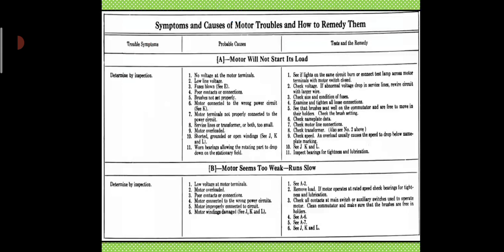Okay. If these problems occur, the tests and remedies are: see if lights on the same circuit burn, or connect a test lamp across the motor terminals with the motor switch closed. Check voltages if there is abnormal voltage drop in service lines. Rewire circuit with larger wire. Check size and condition of fuses. Examine and tighten all the loose connections. See that the brushes seat well on the commutator and are free to move in their holders. Check the brush settings. Check nameplate data. Check motor line connections. Check transformer. Check speed. Overload usually causes the speed to drop below nameplate marking. See the belt and coupling, and inspect bearings for tightness and lubrication.